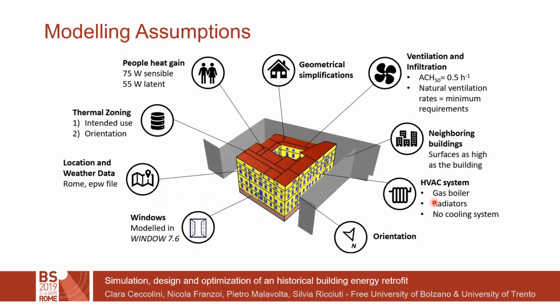One of the most challenging aspects we faced during the project was to realize a reliable simulation model. Indeed, the little information provided in the briefing documents forced us to make several assumptions. For instance, for what concerns the natural ventilation rates, we believed an airflow simulation would be far too detailed to obtain reliable results, given the little information we had. Therefore, we set up the ventilation rates equal to the minimum requirements, also in view of guaranteeing acceptable indoor environmental quality.